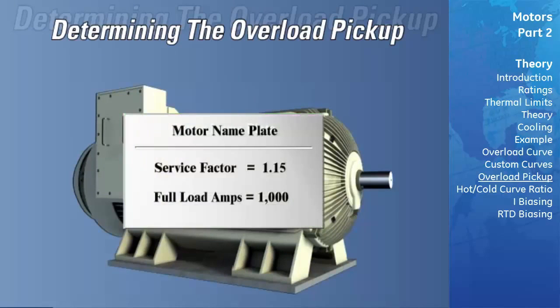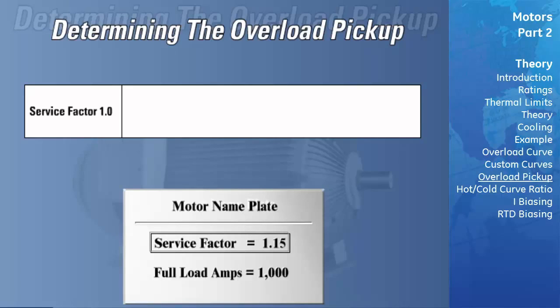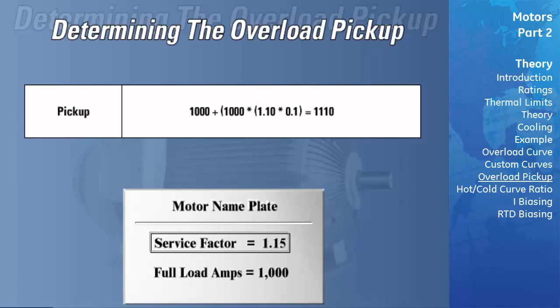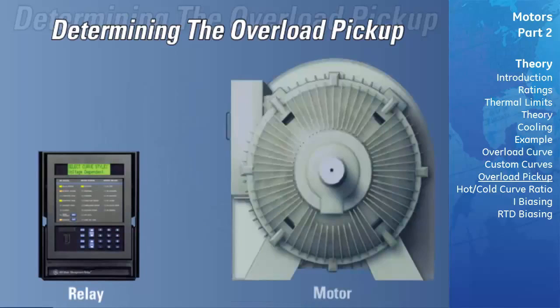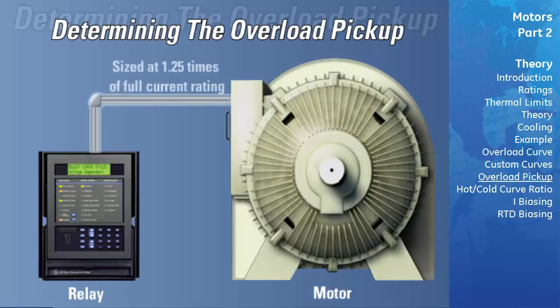Determining the Overload Pickup. The protection engineer will typically set the overload pickup to 100% of the motor's capability. For motors with a 1.15 service factor, a maximum pickup of 125% of the full load current can be selected, while the maximum pickup for 1.0 service factor motors is 115% of full load current. It is common practice to set the pickup to no more than the rated motor full load current plus no more than 10% of the service factor, unless there is an independent measure of motor temperature such as stator RTDs. Note that the motor feeder cables are normally sized at 1.25 times the motor's full load current rating, which would limit the motor overload pickup setting to a maximum of 125%.